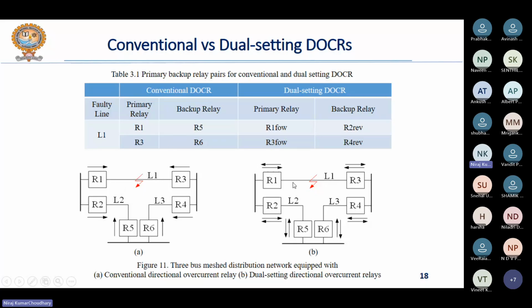conventional directional overcurrent relay. Now, in this figure B, we have replaced the conventional DOCRs by dual setting DOCRs, that is dual setting directional overcurrent relays. So you can see that there are two arrows above each relay, right? Above R1, you can see two arrows. This means that this relay will sense the fault for both directions of current, that is forward direction and reverse direction, right? So for the same fault location at L1, if R1 is considered as the primary relay, then what will be the backup relay in this case, in the case of dual setting DOCRs?